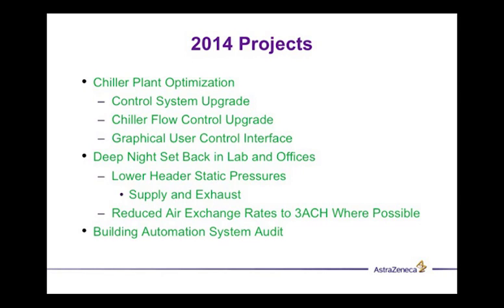Deep night setbacks in the laboratories and offices. Supply and exhaust, reduced air change rates at 3 air changes. So we lowered the static pressure in the header, and what we found is actually a really simple thing, and I think a lot of people know about this.